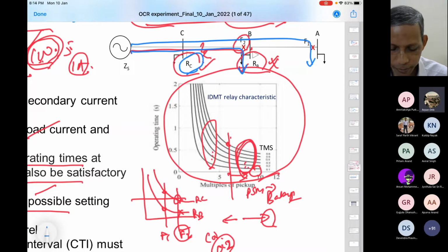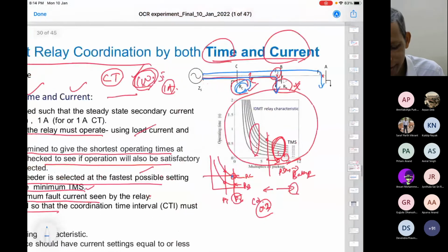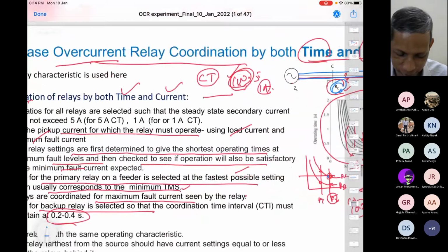When we are determining the coordination time for RC, won't it also affect the trip time for F2? Yes, the entire curve will be affected. For RC, it is affecting. So that's a delay. I told you that. That is a demerit of the system. Yes, understood. Very correct, sir. So it is a delay in the system. But if you don't do it, then backup cannot be provided. Is it okay? So that's the demerit of this. What you say is very correct.